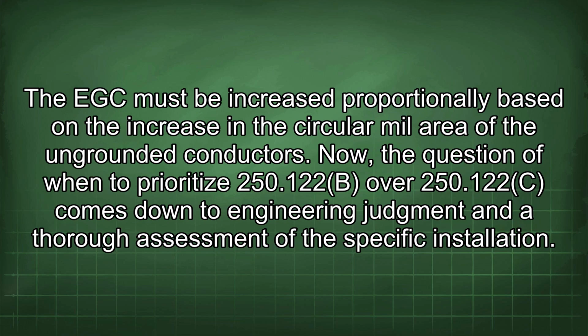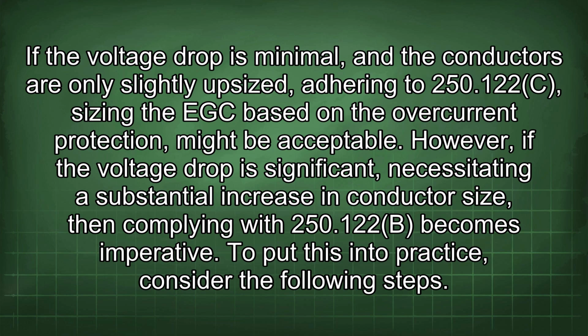Now, the question of when to prioritize 250.122(B) over 250.122(C) comes down to engineering judgment and a thorough assessment of the specific installation. If the voltage drop is minimal and the conductors are only slightly upsized, adhering to 250.122(C), sizing the EGC based on the overcurrent protection, might be acceptable. However, if the voltage drop is significant, necessitating a substantial increase in conductor size, then complying with 250.122(B) becomes imperative. To put this into practice, consider the following steps.